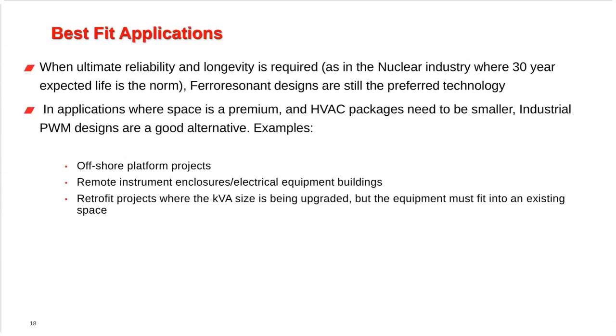Before I go on to the next question, we have been asked, how long will AMETEK continue to build ferro UPSs? There is no discussion whatsoever that I know of that we will ever stop building ferro-resonant systems. We have changed the technology a little bit. We do use the same display board as the DPP system now, but the inverter technology is still a square wave at line frequency and still goes through a CVT ferro-resonant transformer, and is still very, very robust. And as far as I know, we have no plans whatsoever to stop building ferro-resonant UPSs.